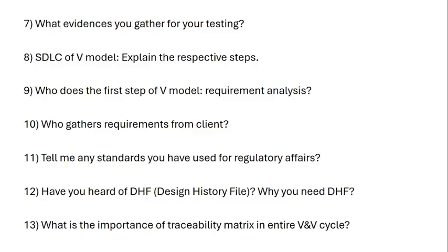So why do you need DHF? Here, DHF is nothing but the design history file. In the medical domain, the design history file is the total documentation of a finished medical device from start to end: how the design happened, how testing was done, how certification was done, everything. For a finished medical device, it is the total documentation, and how the design and requirements came about, everything it will contain. So that is called the design history file.